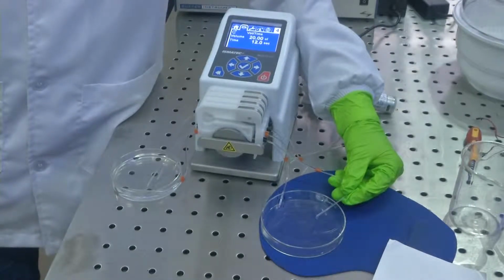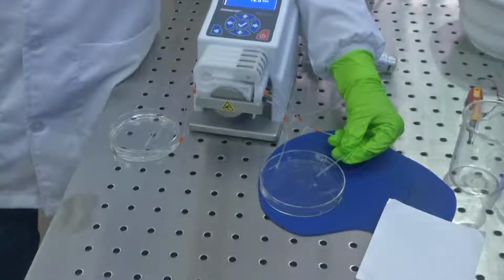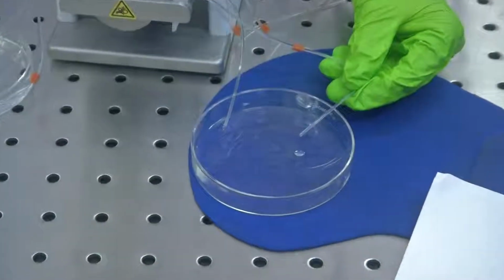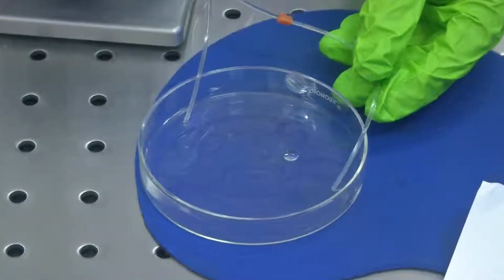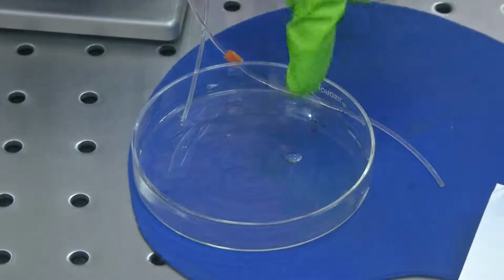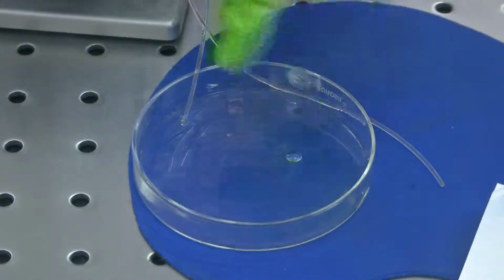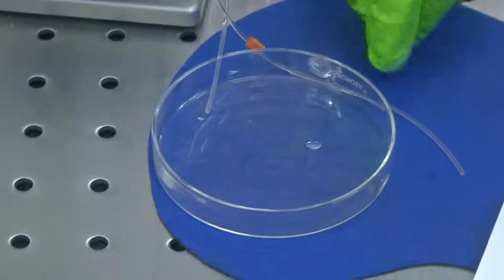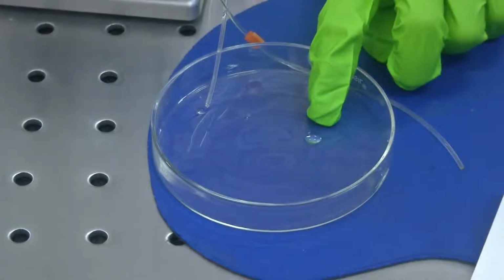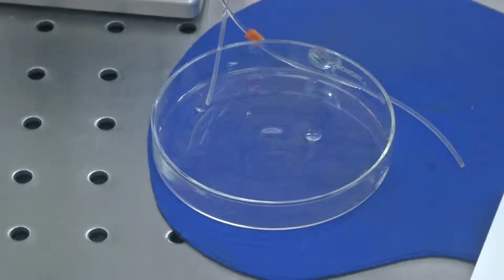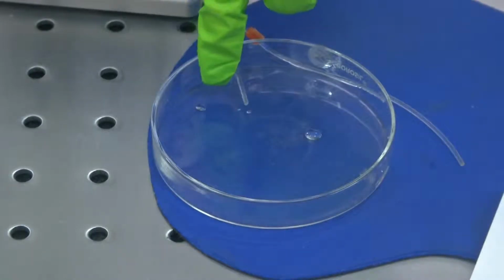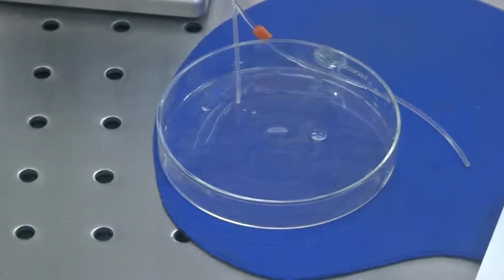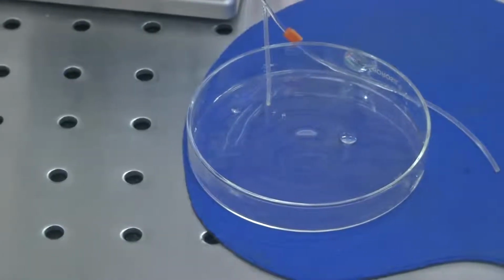So, now that you have seen, we have done the setting. So, in the 3rd cassette we will have some 5 microliter of fluid, and the 4th one is 20 microliter of fluid. As you can clearly observe the volume of fluid which is coming out of the channel. Here, as you can see, there is this 4th channel with a higher volume.